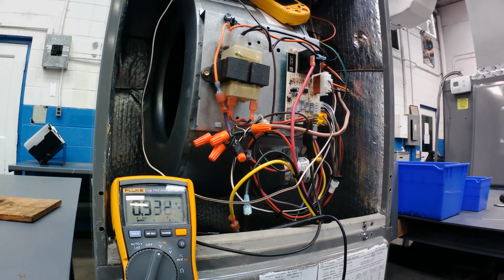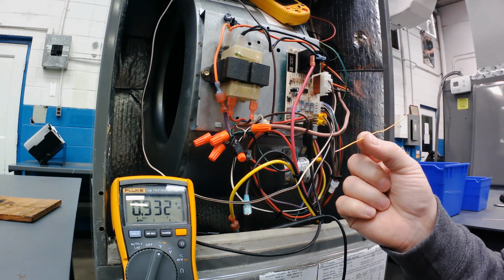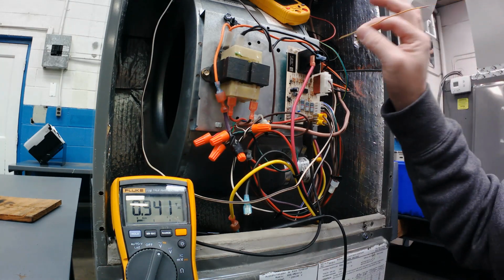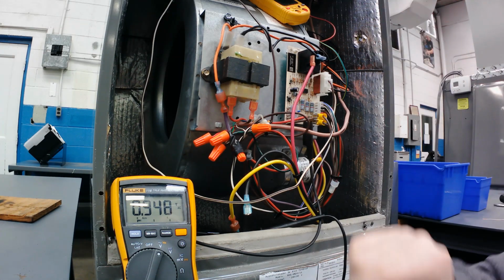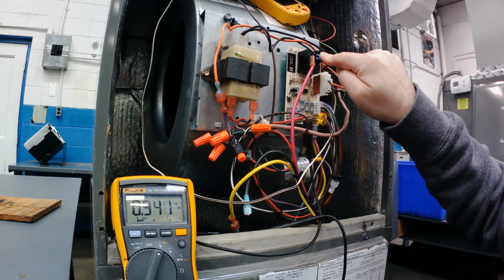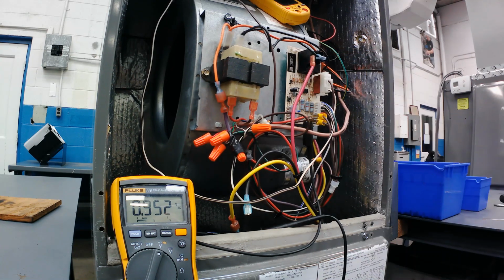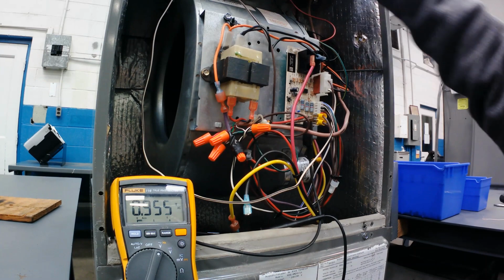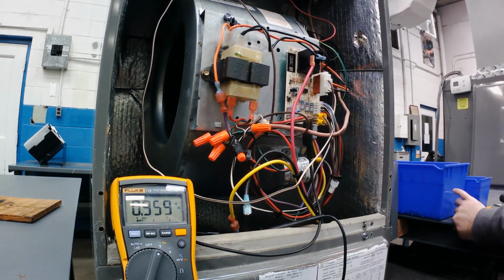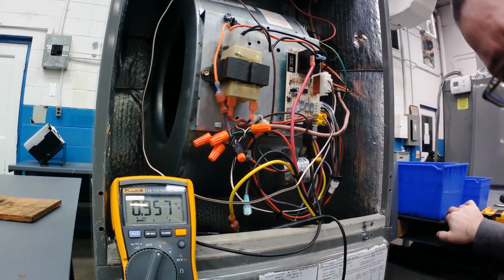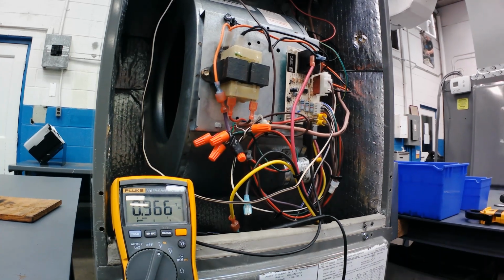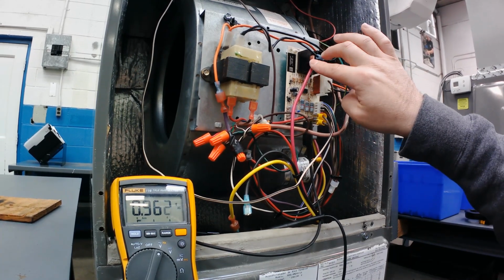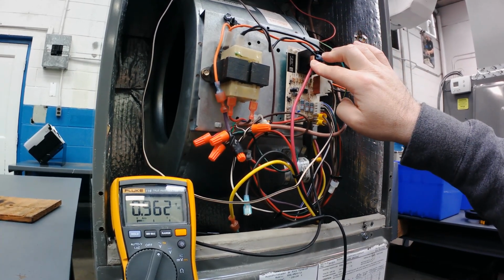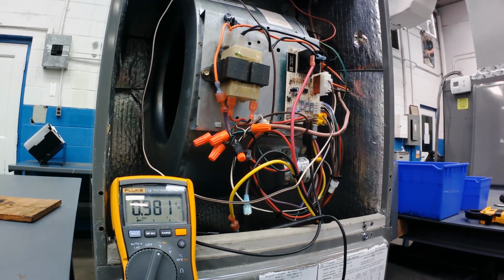As far as your high voltage, I would not stick the thermostat wire in the high voltage portion of the relay. Usually those are insulated terminals like here. They are not necessarily going to give you enough room to put in there. You could try it, I guess, if you really want to, but I usually don't. If I want to see if power's going in, well, for one, we can hear it, so we know it is. And since this is the only switch on this particular relay, it's pretty safe to say that switch is closed when it's supposed to be.